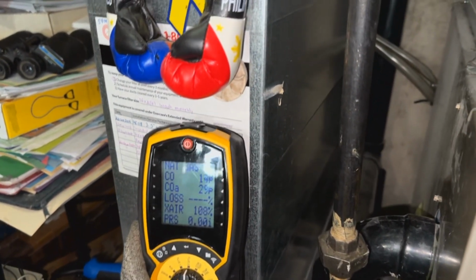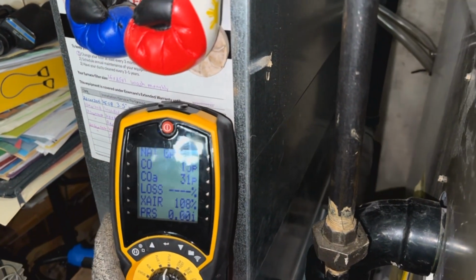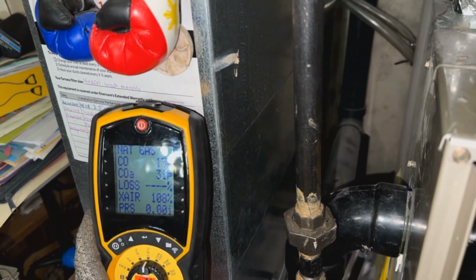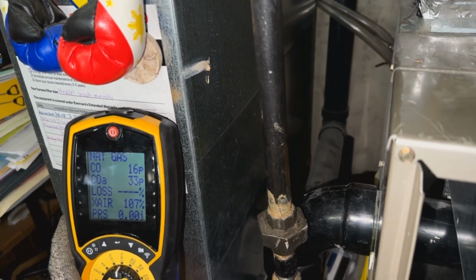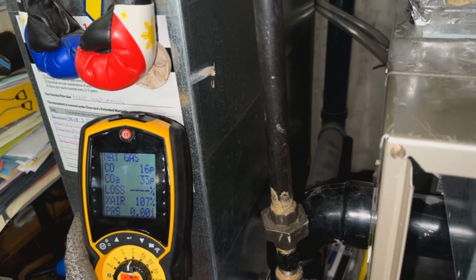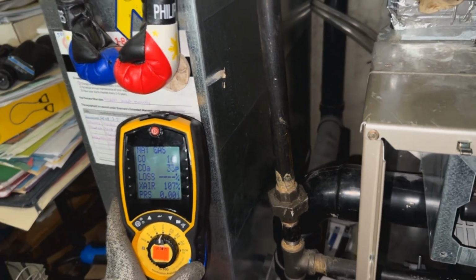And as for CO readings, we're at 15 parts per million right now. So for the most part, the same reading as outside. So I'm confident this furnace isn't going to kill us. Yeah, everything's good. Golden. A little better. So that's it for the furnace maintenance.